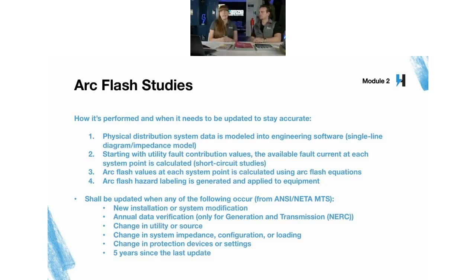Oh, for sure. Now, the idea is whether or not there's going to be enough of a change to cause your overcurrent protective devices to react differently. Maybe they trip slower. If you have less available fault current, that's potential. Or if you get over a certain threshold and you just keep going up and up and up in the available fault current, your hazard can get worse and worse, right? So unfortunately, most of the time, they're not going to give you that heads up. You have to request that information on a regular basis.